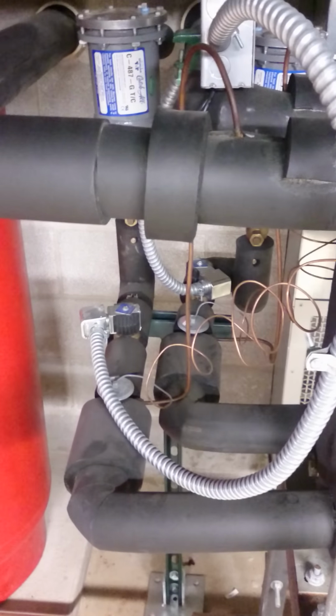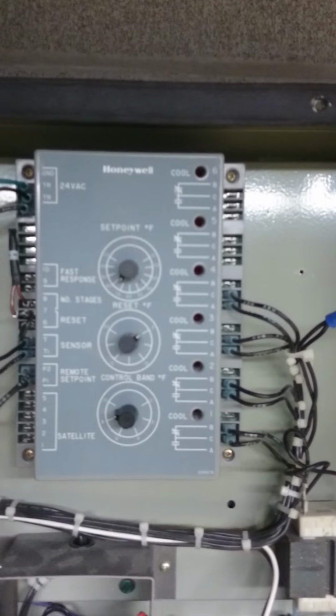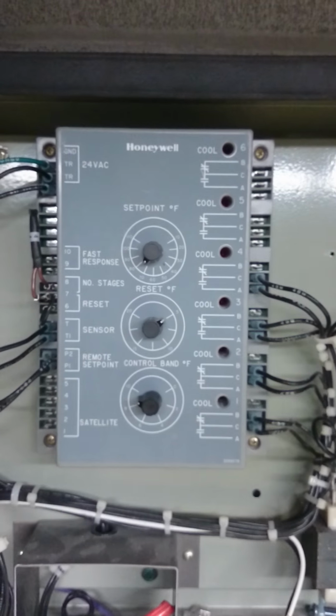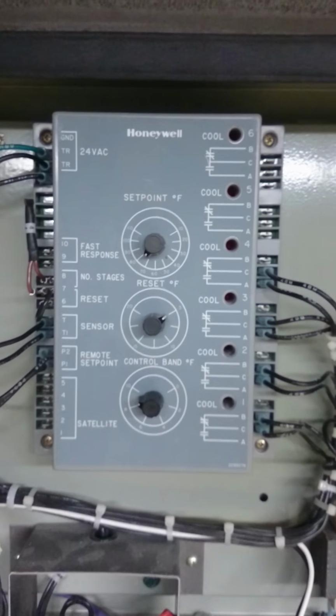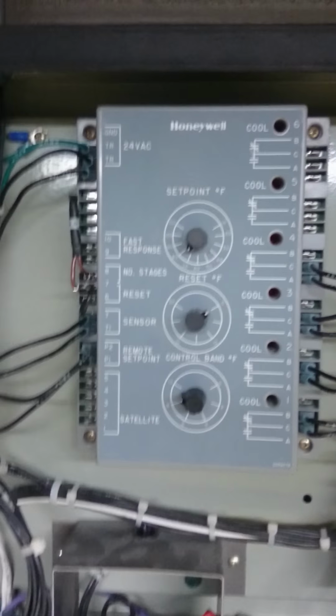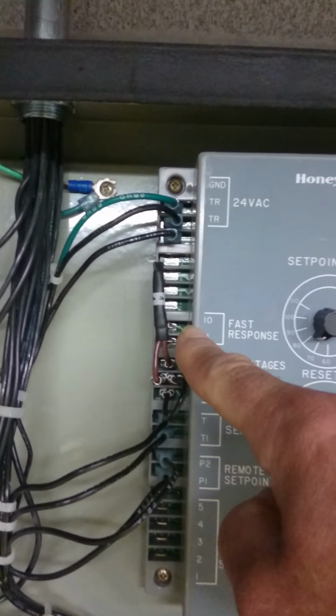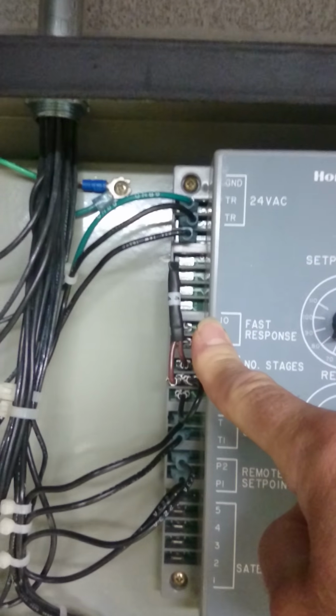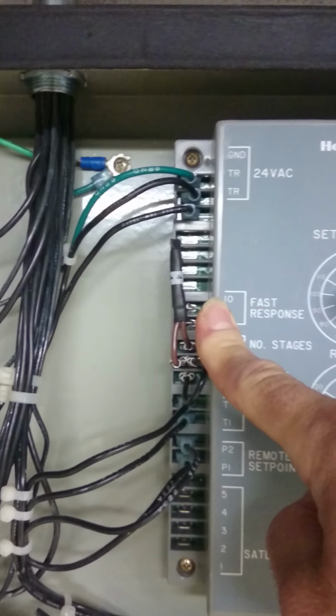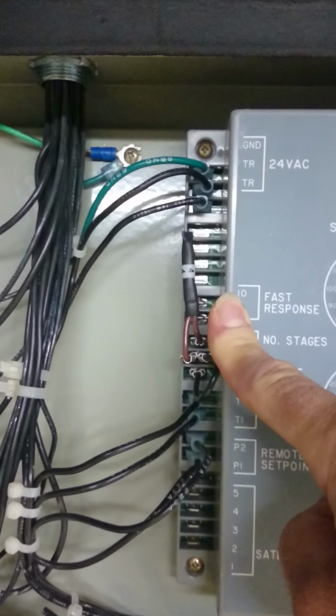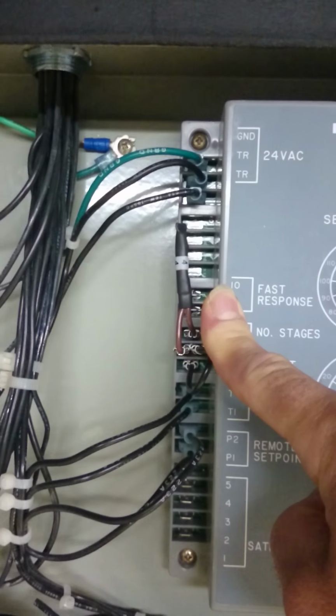We've got two refrigerant circuits, and each circuit has two compressors. So this would be a 4-stage unit. First thing I found when I came out here is we've got a stage controller here that stages on each stage of cooling required. I did find that we had an incorrect resistor installed in it that was telling this controller that it was only a 2-stage unit. So we had to order in some resistors and install this 401 ohm resistor here to tell this controller that we have 4 stages.